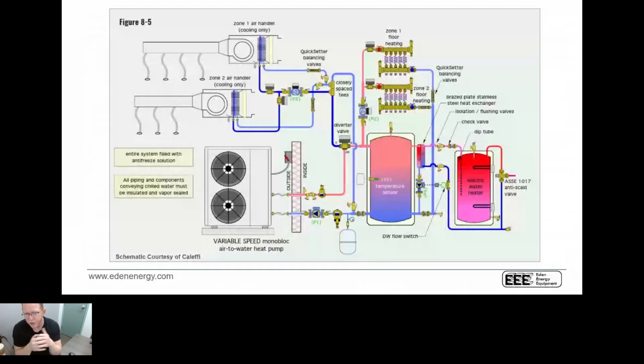This last method, and this is a method that we use using the HPX5 and the Sky 35 controller I showed you earlier, is the Sky 35 controller has the ability to control the heat pump. It'll control the indirect, both heating and cooling. And in this particular case, it's a diverter valve. So the idea being that if we ever have a cooling call, we're going to actually divert, not charge the buffer tank, and deliver the coldest water possible into the air handler.